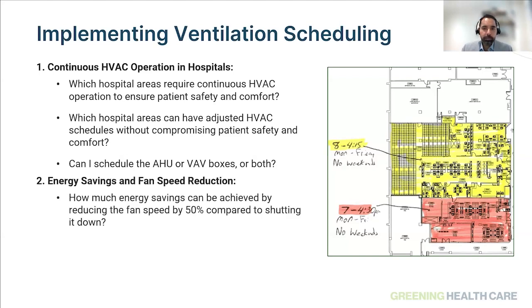Other questions that come in are, do we have to completely shut down these fans, or shall we schedule them at a reduced speed? What's the difference in energy savings? Typically, when you reduce the fan speed by 50%, you're reducing the energy consumption by almost 80%. Whoever you work with is going to determine your lowest point of fan operation, so it could be done either way. You could reduce the speed, or you could completely shut down the system depending upon the type of space, but it is doable. The safest thing in most cases is to start with reducing the speed before you shut down the complete systems, because it still gives you the opportunity to mitigate pressurization concerns, and you've already achieved 80% of the fan power and most of the thermal savings by doing that.